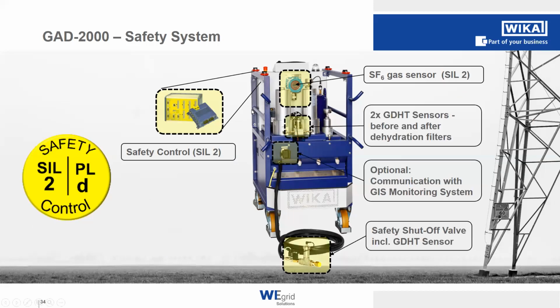And we have, as an addition, 2 GDHT sensors before and after the dehydration filters to just make sure the dew point or the dew temperature is at a certain level. And then we also have optional communication, which is directly connected with the gas compartment, with the gas density sensor at the gas compartment. If we get a signal from the gas density monitoring system or the gas density sensor mounted to your compartment, we can immediately shut off the connection between the gas compartment and our GAD. The magnetic valve will react and seal the connection completely.